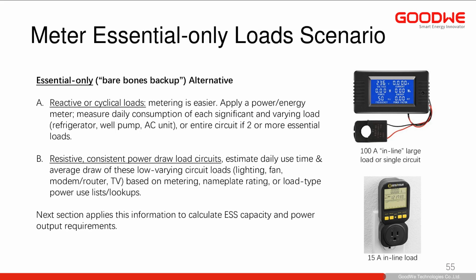Understand that most of your resistive loads will not vary a lot, so just getting nameplate rating off them will help you. Although a lot of different types of loads that we call resistive are variable resistive. LED lights, even the old incandescent lights, when the filament is cold, that tungsten filament is highly conductive. But the moment it starts to heat up, it becomes highly resistive. So there's a great inrush of current initially. So there are a lot of inrush current devices. It's the ones that are high in nature that you care about. Don't worry about the lights.